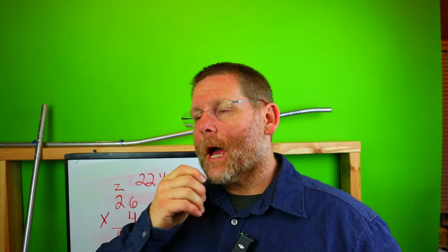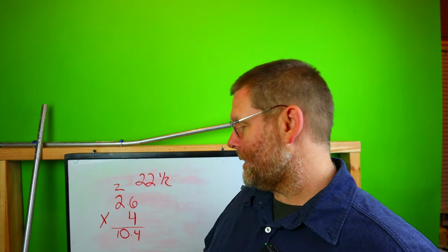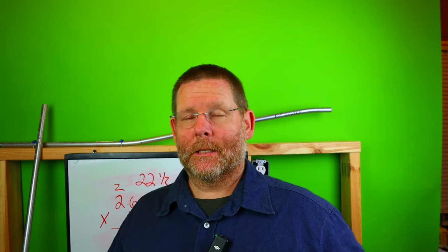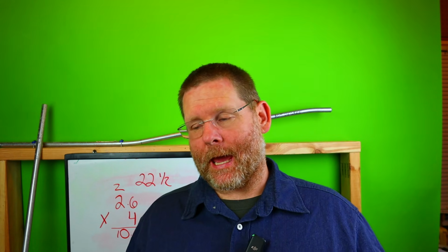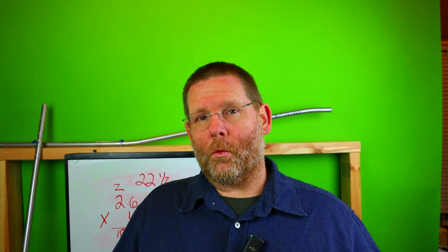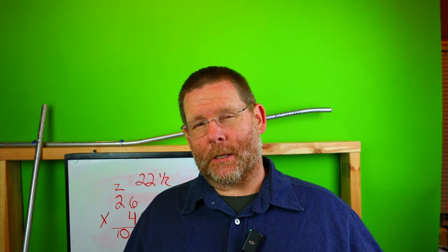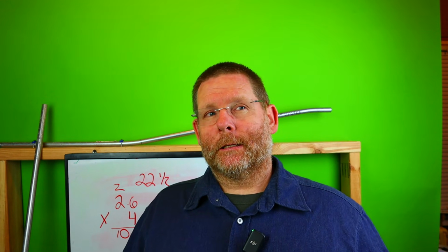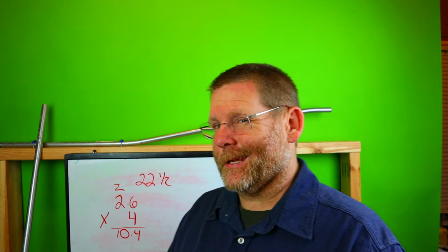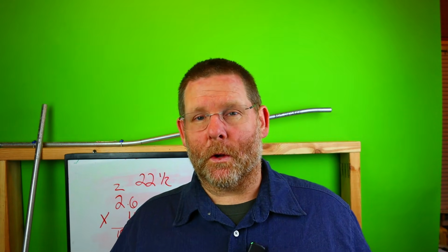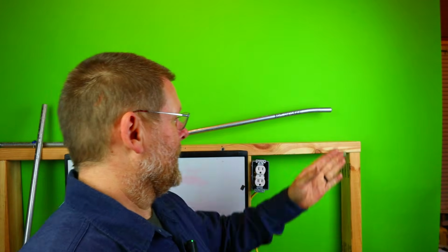Now, I'm going to go out on a limb here and say that from the last video I did, you can probably use the math to do this. I will say that usually what normal electricians will do, I mean, there are some that try to be really, really precise, most of them will just eliminate the 0.4 and just say 10 inches between your marks. That's up to you if you want to do that or not. I'm just going to leave it at 10 inches, and I can almost guarantee you that it will be 4 inches by the time I get done. Not, we'll tweak it, but we'll see.